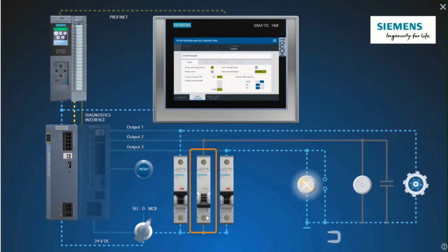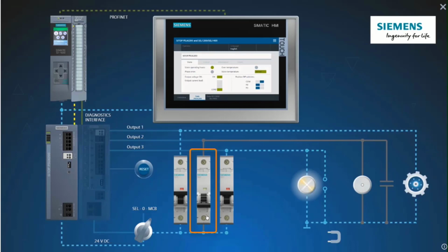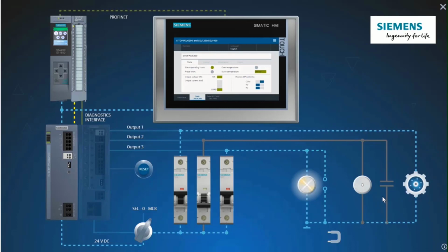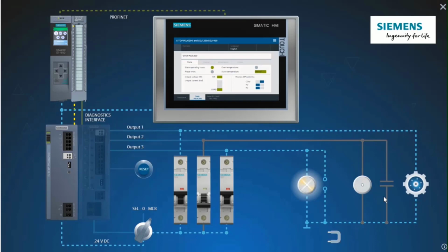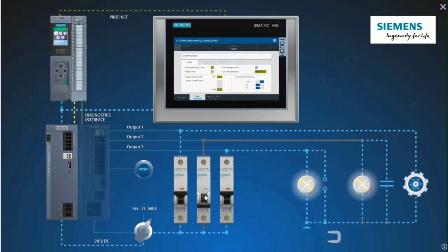Although the 2 ampere circuit breaker is designed in characteristic C, this is for high inrush currents, the capacitor cannot be connected. The unintentional tripping can also happen when switching on electromagnets or DC motors. Only by switching on the miniature circuit breaker several times can the capacitor be successively charged and switched on.